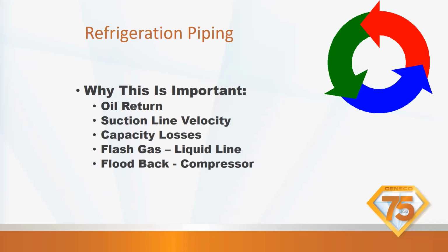Okay. Flash gas. If you have flash gas in your liquid line, you're not going to have liquid at your metering device, and you have to have 100% liquid at your metering device or you lose capacity big time. Flood back to the compressor. If you have flood back to the compressor, you're going to kill your compressor. Liquid in the compressor, bad news, right? Everybody knows that. We cannot compress a liquid. That's why they sound so bad when you get liquid in them. And if you're charging and you hear the compressor starting to make noise, slow down your charge. Shut it off for a minute until the noise goes away. Start again very slowly.